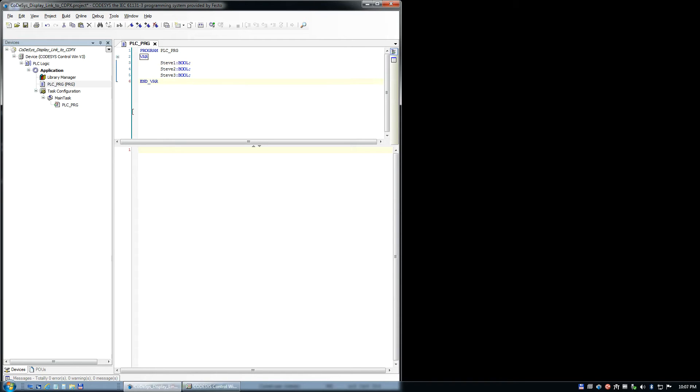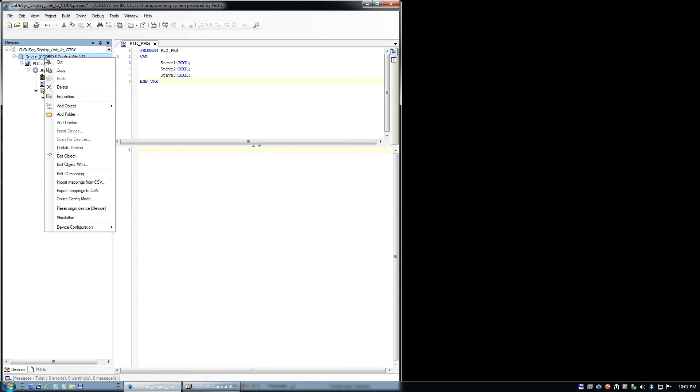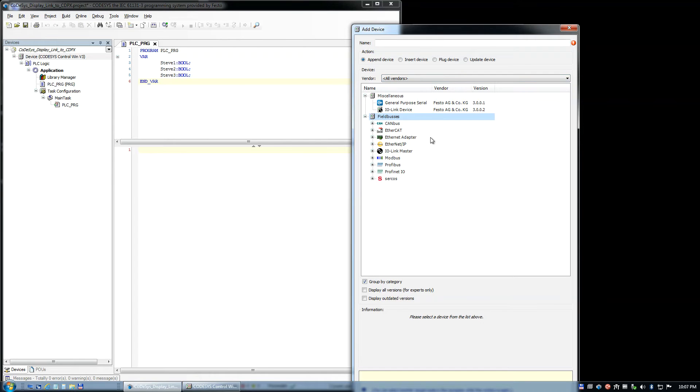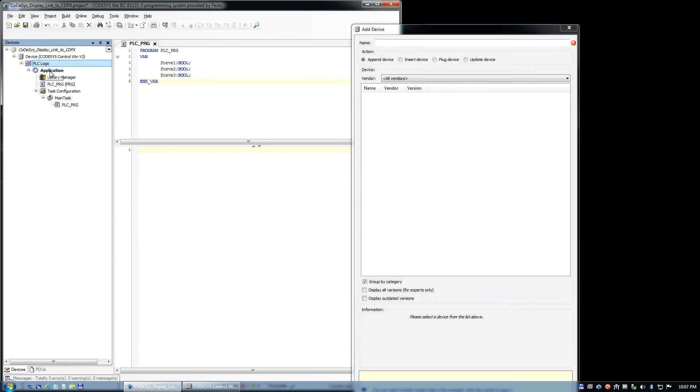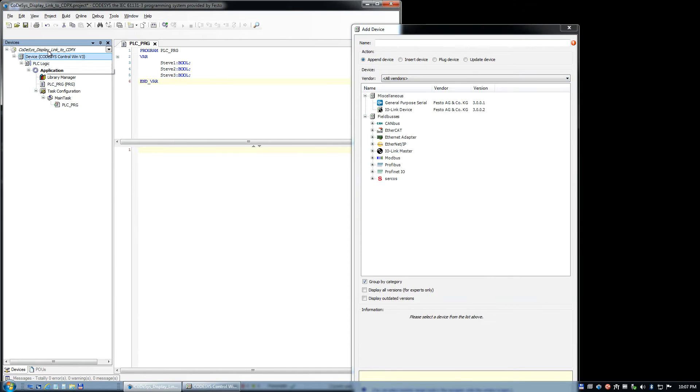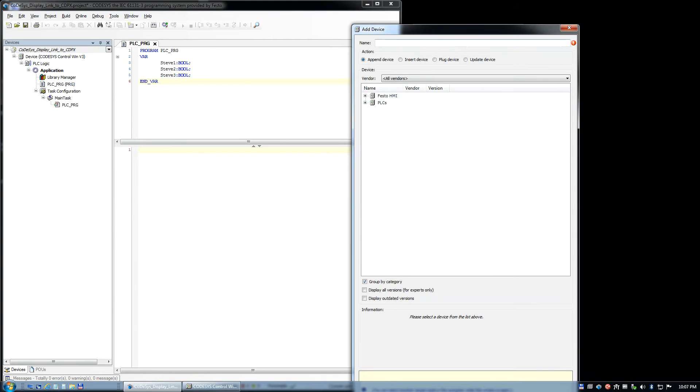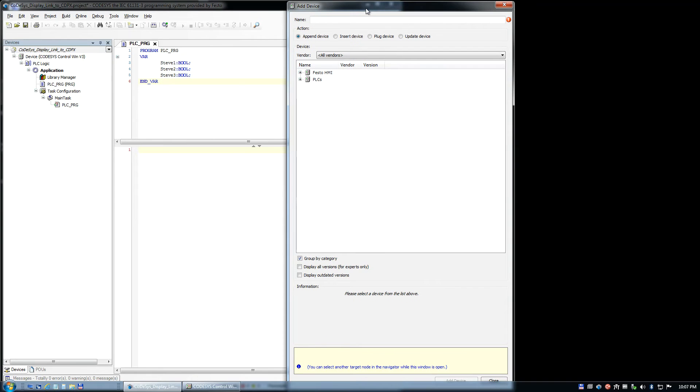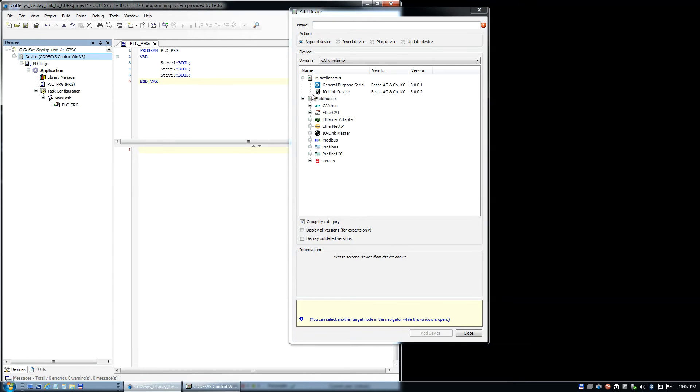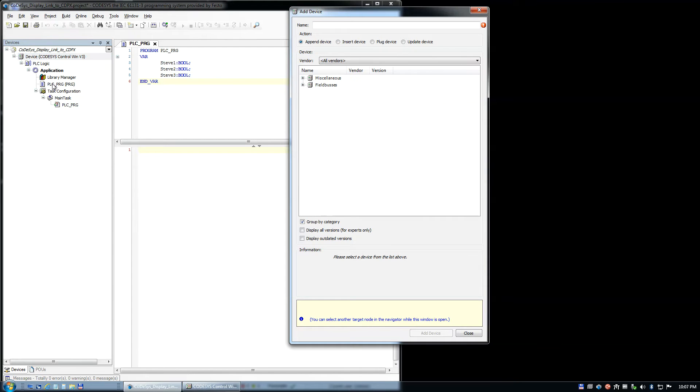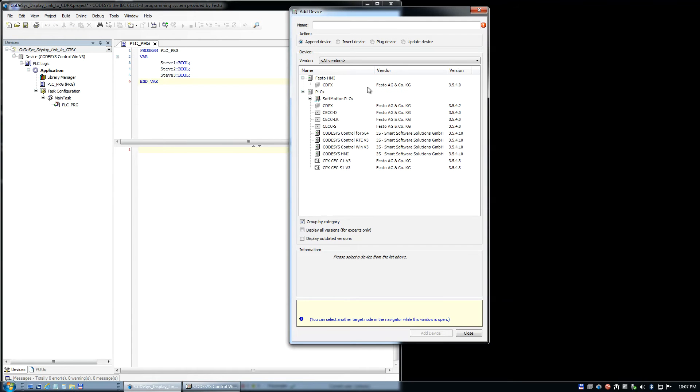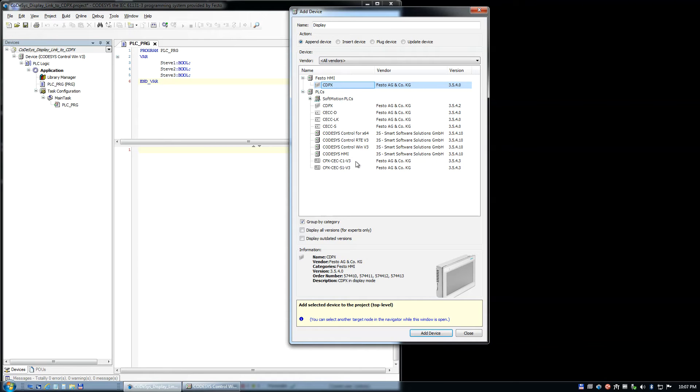Now we need to add an object, device, miscellaneous, field bus, all vendors, application. As you see here, this is important to understand. Depending on where you've clicked in the project, it only gives you certain options. If you click up here, you don't get the option that I'm looking for right now. You need to click at the very top. What we're looking for here is a Festo HMI. You could come through here and select things a little differently, but this is how I like to do it.